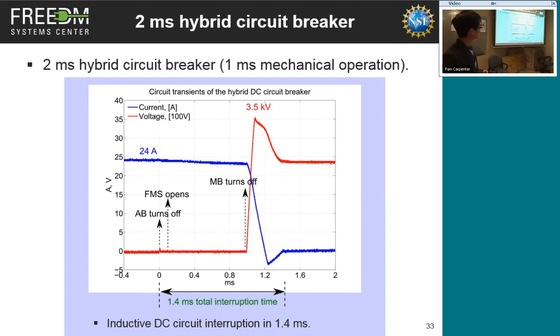We also tested this hybrid circuit breaker. We tested at a relatively low current, 24 amps, but with a transient recovery voltage at 3.5 kilovolts. It's a pure inductive circuit interruption - there's only an inductor in that circuit to interrupt. So that's pretty close to the real application of DC circuit breakers. The total interruption time is 1.4 milliseconds.